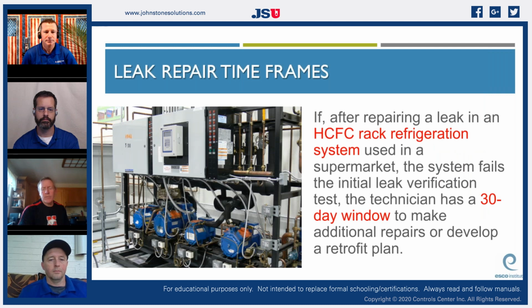This slide, I think, is you, Clifton. Yeah, that's me. HCFC rack refrigerant used in a supermarket. The system fails an initial leak verification. The technician has a 30-day window. I believe, Clifton, you have to check these big racks that hold a lot, like over 1,000 pounds, every 30 days or 90 days.